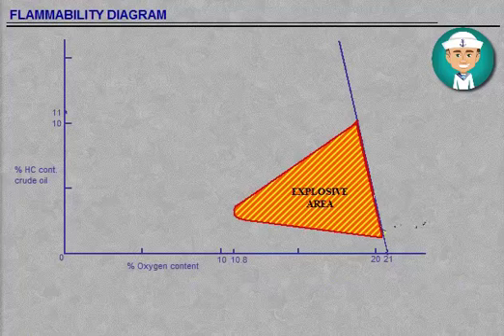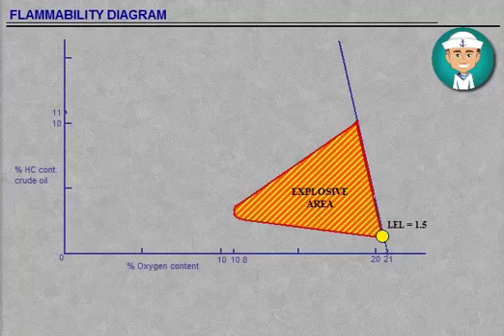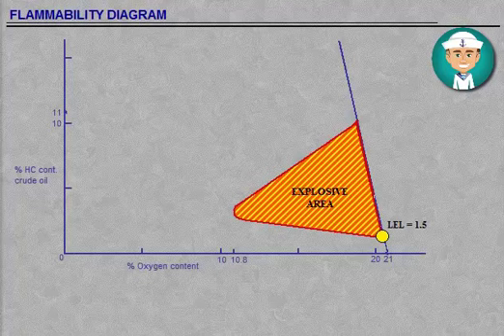The lower limit of this range is known as the LEL, lower explosive limit, also known as the LFL, lower flammable limit. This level means the hydrocarbon concentration below which there is insufficient hydrocarbon gas to support and propagate combustion. The mixture is said to be too lean.